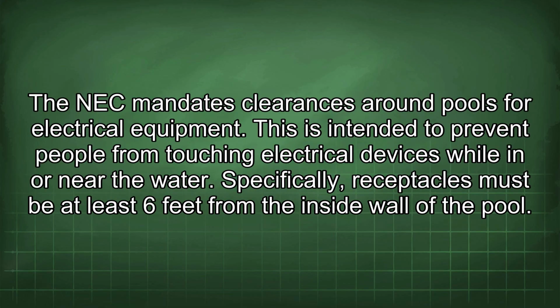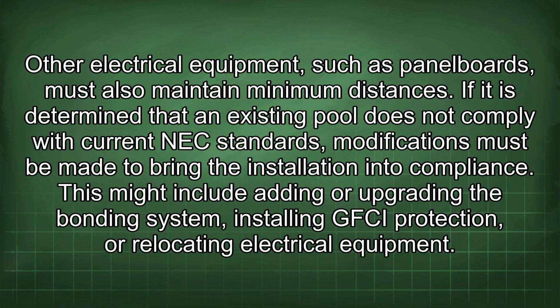The NEC mandates clearances around pools for electrical equipment. This is intended to prevent people from touching electrical devices while in or near the water. Specifically, receptacles must be at least 6 feet from the inside wall of the pool. Other electrical equipment, such as panel boards, must also maintain minimum distances.